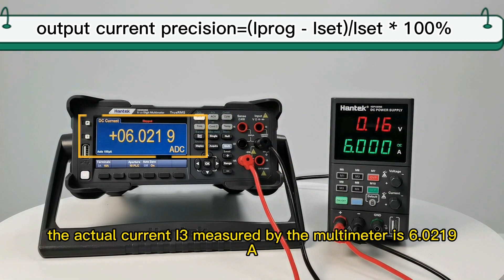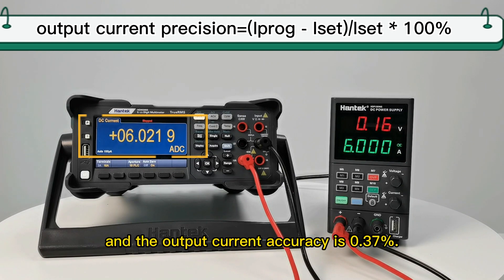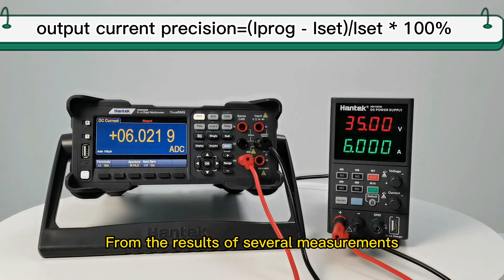The actual current I3 measured by the multimeter is 6.0219A, which is brought into the formula. The output current accuracy is 0.37%.